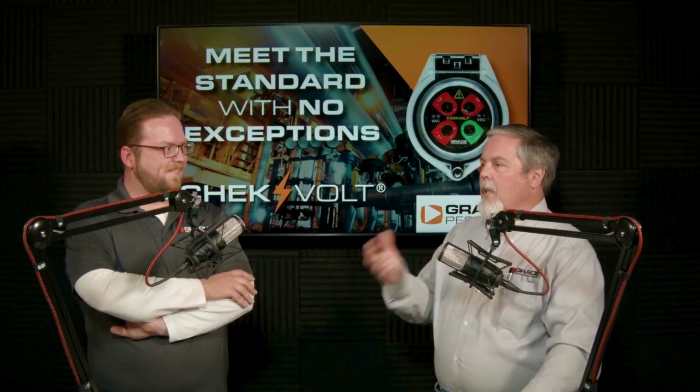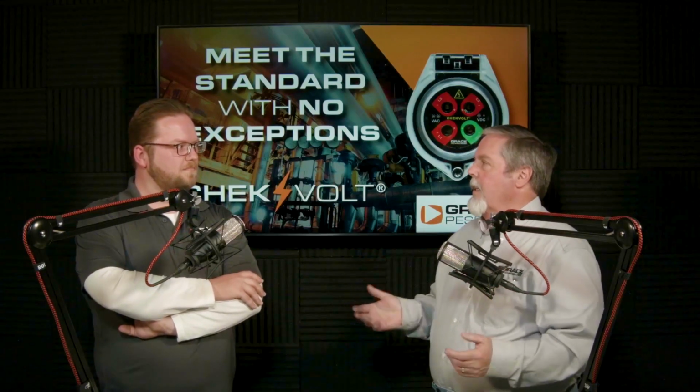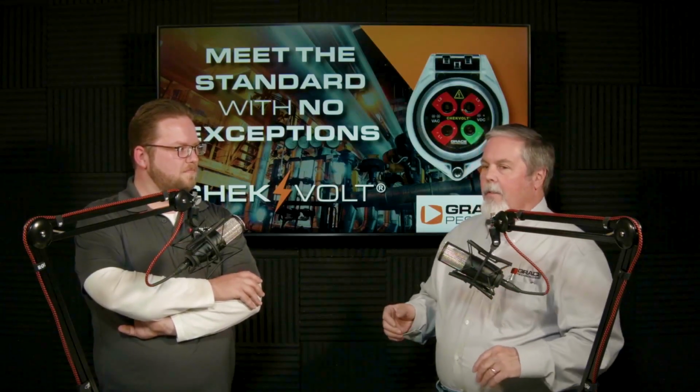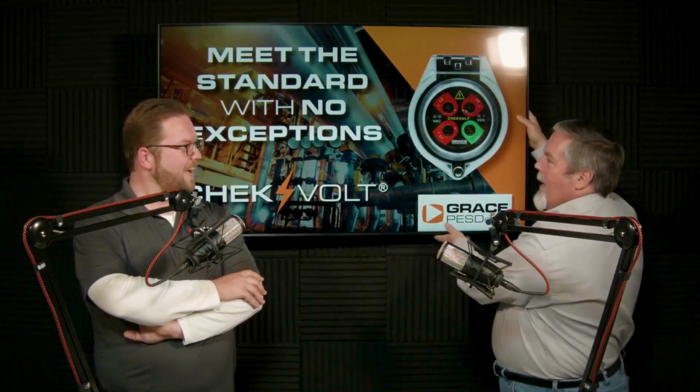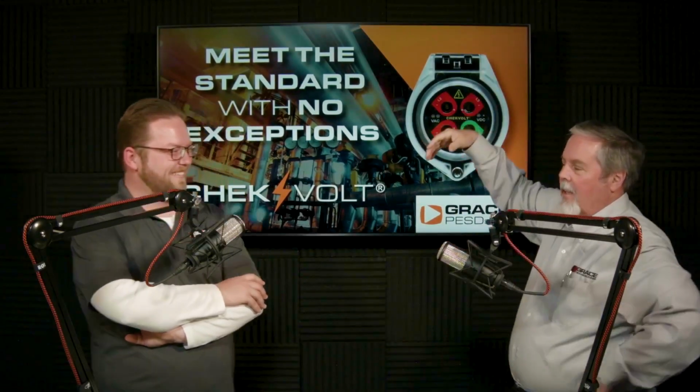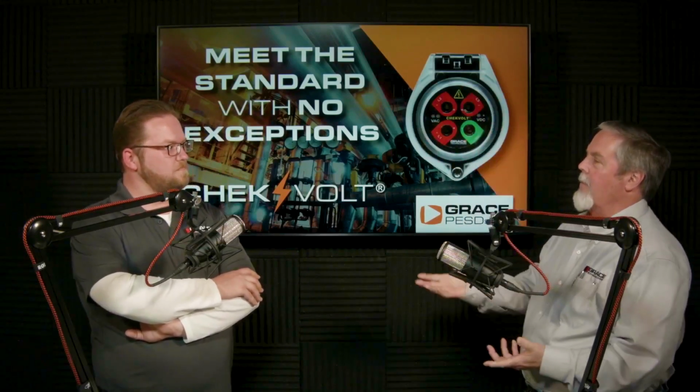In that respect, I mean, you think about it. So if somebody comes up to a cabinet and they really don't know what's inside the cabinet, but they feel authorized to push a button, they can open up that cabinet, and the first thing they do is they get in the cabinet and they put their hand on top of the disconnect. Yeah, that happens. And exactly. They're now touching the incoming source, the live conductors. That could be 480 volts at several hundred amps, but they don't know that that hazard exists. So they shouldn't be in the cabinet to begin with, but they felt authorized to be able to push a button.